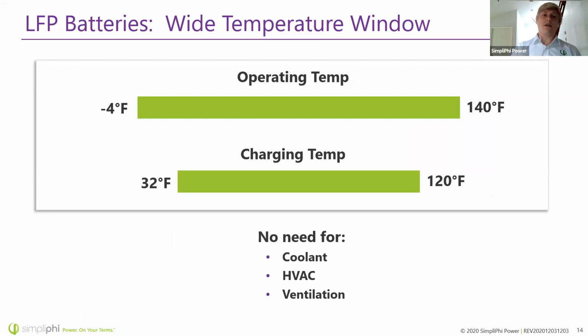Lithium iron phosphate batteries also have a very wide temperature window. They can be stored or discharged from -4 degrees Fahrenheit all the way to 140 degrees Fahrenheit. For charging, the batteries cannot be charged below freezing or above 120 degrees Fahrenheit, but that's still a wider window than anything else I've seen on the market.